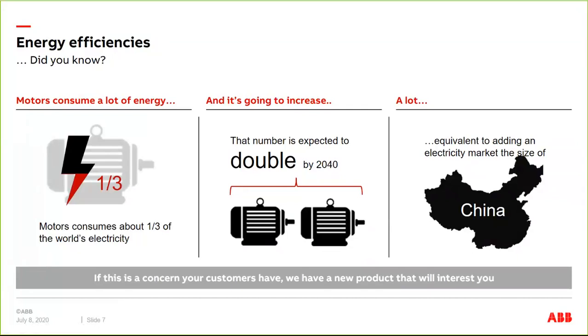So this product is directly there to help overall system efficiencies in your designs and meet new emerging system efficiency regulations, which primarily were originally more on the components, so driving up the efficiency of just the motor itself. But new legislation that's coming on, and it's kind of in a staged approach. So if it's in the fan market or the HVAC market, it's not across all units, but it might be starting in roof-mounted air handling units. And in the pump market, it's not all pumps, but we're seeing it emerge in, let's say, pool pumps or something. But it's really driving total system efficiency.